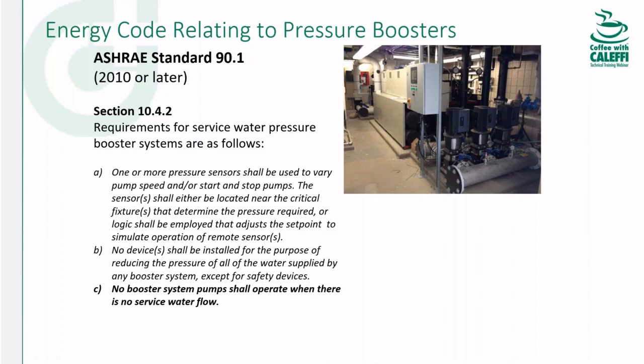And then no devices shall be used to knock down the pressure for all the water supplied to the building. So your primary booster system that's supplying water to the building should not have any pressure regulator valves on it. Not to be confused with PRVs that are knocking down pressures on floors in multi-story buildings. They're just saying no PRVs on the pump station itself that's supplying the water.